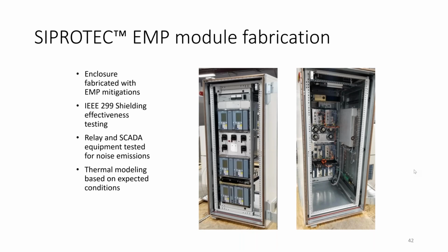We decided that the SIPROTEC EMP module was going to be something that, with minimal modifications, really what we did is add a slightly taller door to the existing control house, and then it sat inside. So you can't tell from the outside of our substations which ones have been protected and which ones haven't been. The other thing is it prevents us from having an incidental compromise of the shield, where somebody doing other work in the control house drills a penetration through the control house wall and now our shield is compromised.